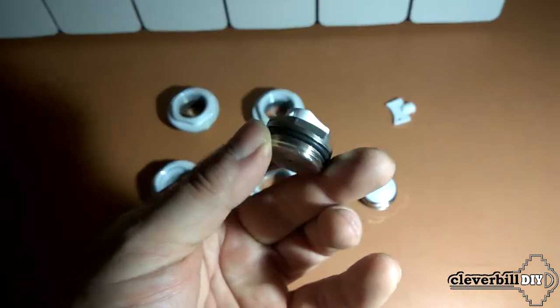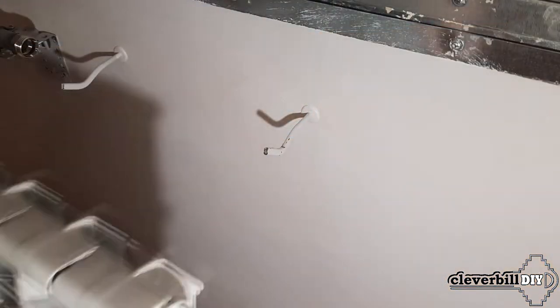Thanks to the Maevsky tap, it is easy and simple to remove air from the system after the coolant is launched into it. To mount the radiator on the wall, I need a set of dowels and brackets. Manufacturers recommend using at least three brackets for radiators with up to 10 sections, where two are located at the top and one at the bottom.